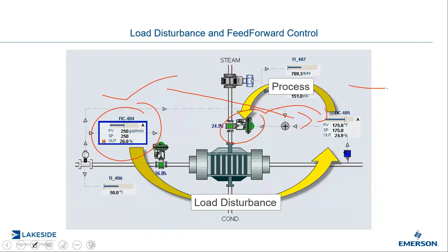To do that, we need to calculate a load gain. Remember, when tuning, we calculate the process gain - the relationship between a change in the valve and how that affects my temperature. That's the process gain. After that, we need to understand the load gain: how much a change in flow will affect a change in temperature.